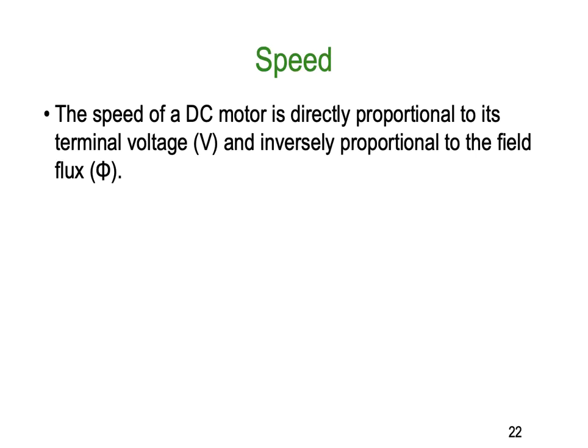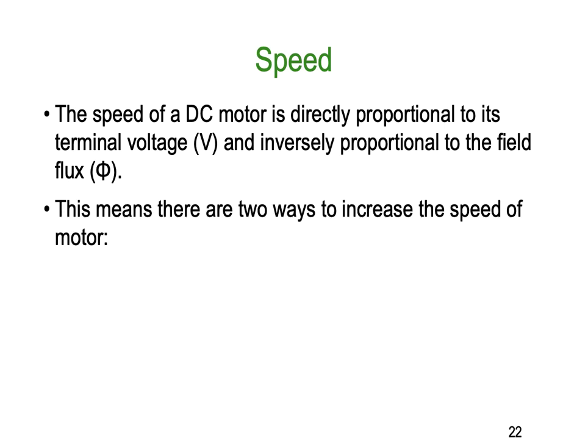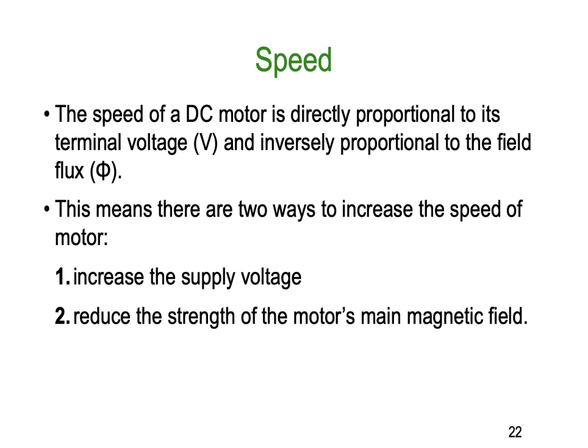The speed of a DC motor is directly proportional to its terminal voltage and inversely proportional to the field strength. If the voltage goes up, speed goes up; if voltage goes down, speed goes down. Conversely, if the field strength increases, speed decreases. This means there are two ways to increase the speed of a motor: increase the supply voltage, or reduce the strength of the main magnetic field.